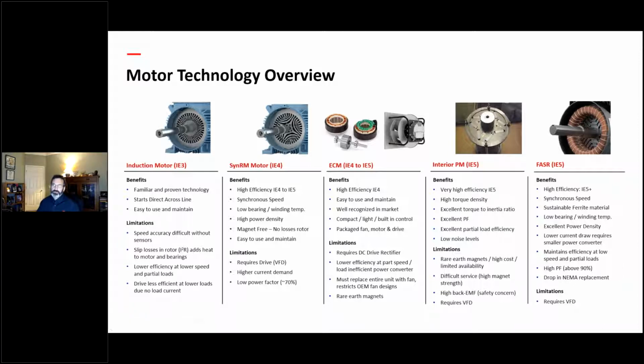The other advantage of it is you can usually drop a frame size. So if a 10 horsepower was in a NEMA 250 frame, you could do this motor design in a 210 frame. So you could get a smaller, lighter weight motor, and that might help you with your structural design. Maybe it doesn't need as much support. It may help you if you're doing retrofits, because two people might be able to rig in a 210 or a 180 frame motor, but a 250 might be too heavy. So, it helps with that.